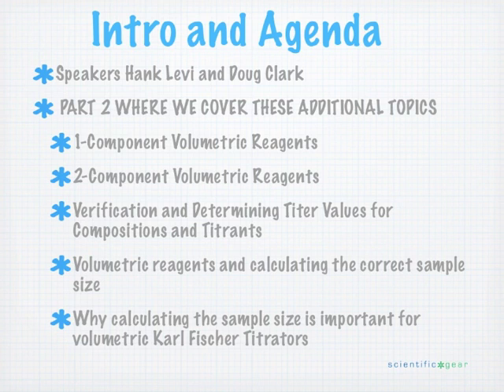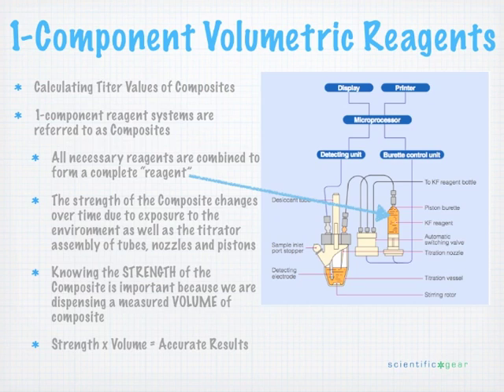When we look at the volumetric system, unlike the coulometric system where the equipment differs — whether we have a diaphragm or diaphragmless generator electrode — the reagents that we use in a volumetric system can be different. We have what's considered a one-component reagent system, which is typically the Hydranal composite reagents. We consider that a one-component reagent because it contains everything necessary for the titration of water, except for the water. So anytime water gets into the reagent, whether it's in the bottle, the burette system, the transfer tubing, or so forth, it is going to react and lower the strength of that reagent.